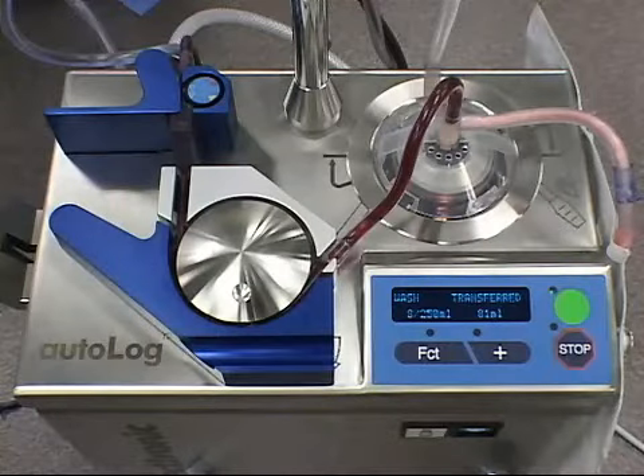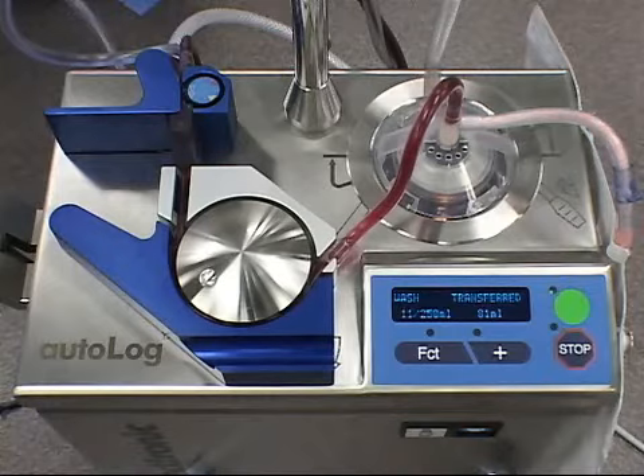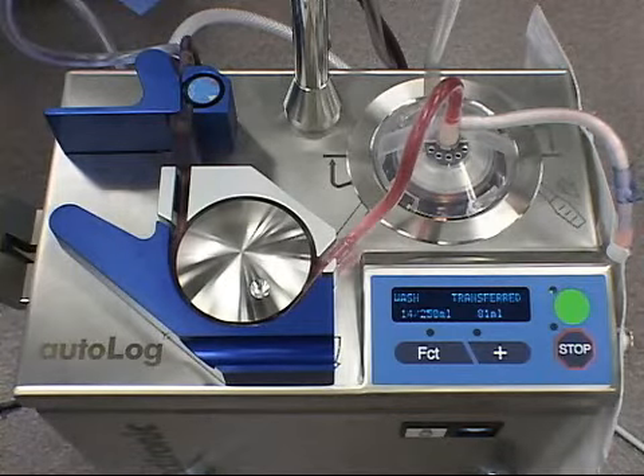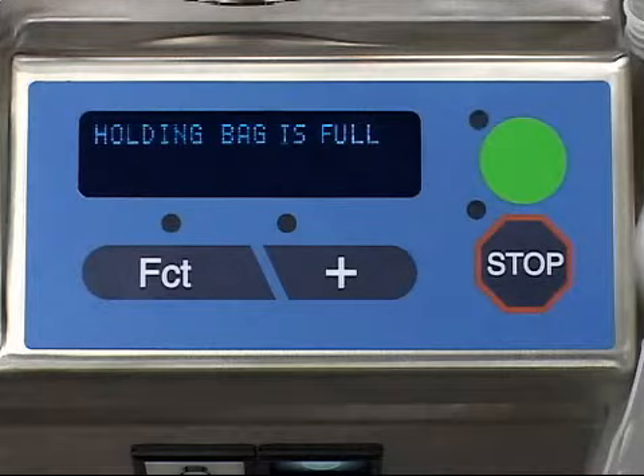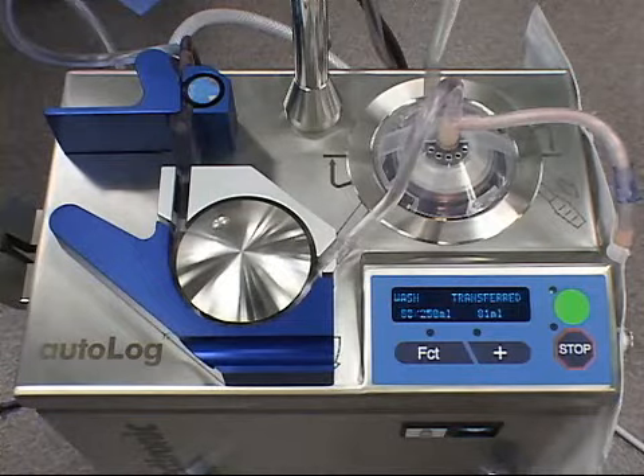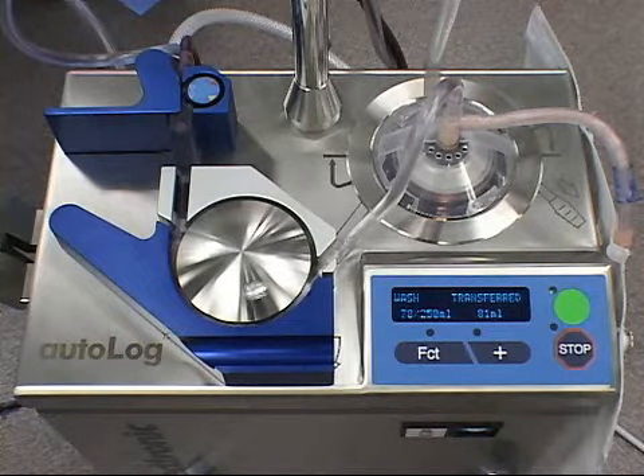After processing 7 to 12 wash cycles, the machine will have filled the holding bag to its capacity. The number of wash cycles is determined by the incoming hematocrit of the blood. The instrument will display "Holding bag is full." Empty the holding bag and reset the display by pressing the green Go button. This will initiate another series of 7 wash cycles.